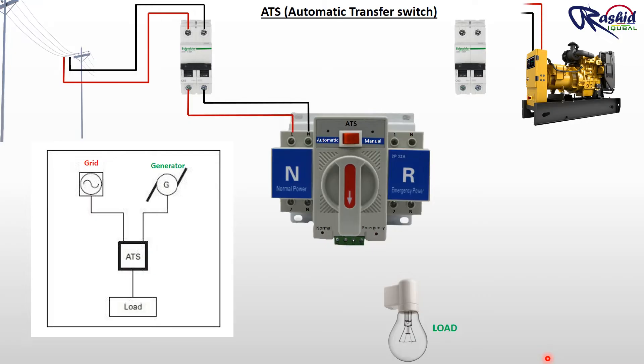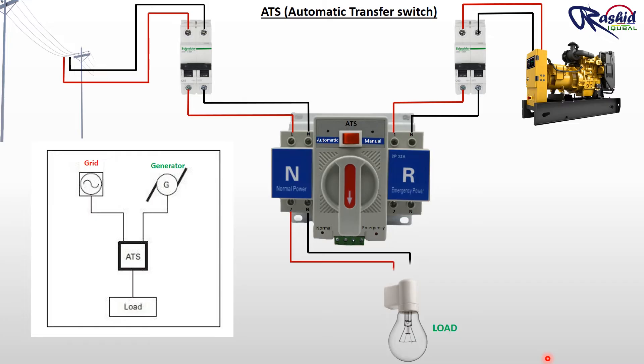Then we take generator power supply to emergency terminal of ATS through MCB. Now from the outgoing terminal of normal power supply we make connection to the load. Same way we connect emergency terminal to the load.